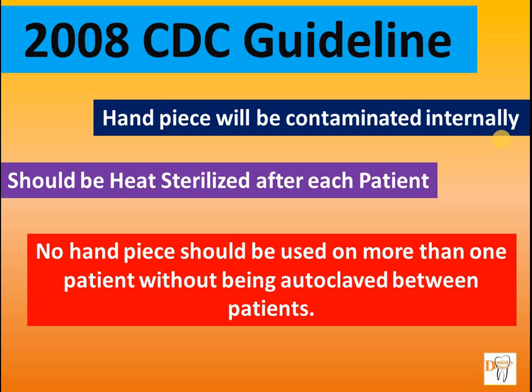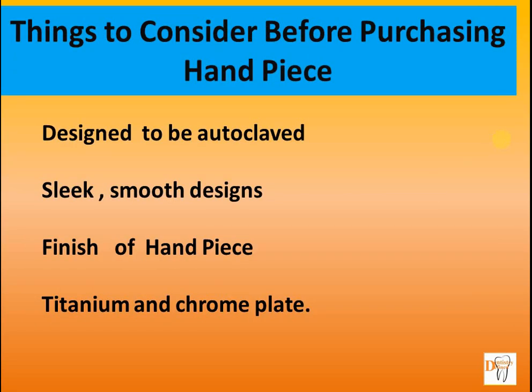Coming on to what to look for in a handpiece from a sterilization aspect. It should be autoclavable and have a smooth and sleek design that does not hold debris and bacteria, and have a seamless finish with no gap between the outer castings. The finish of the handpiece should be able to withstand the sterilization process for a long period of time, and the metal used, that is titanium, withstands chemicals and the sterilization process better than the chrome-plated one.